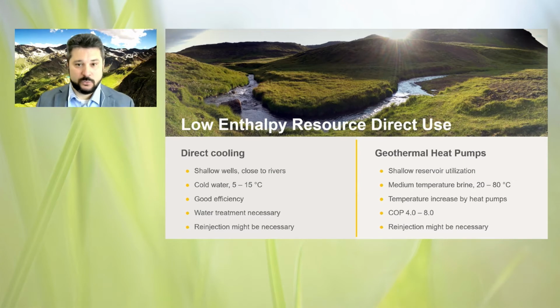Still, what is really used, especially in Germany, are large-scale geothermal heat pump systems. Even high temperatures like 80 degrees could be used for heat pump systems, and the temperature can be increased further to heat even a large district heating system, as I mentioned. The COP, the efficiency ratio of those systems, is very good - can be even 8 or 9. So a very efficient system could be installed utilizing low or medium temperature geothermal brines for providing heating energy.